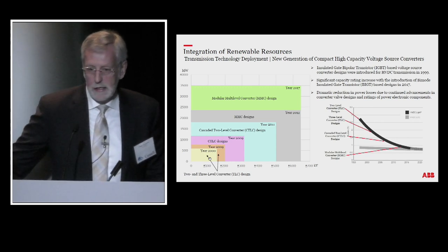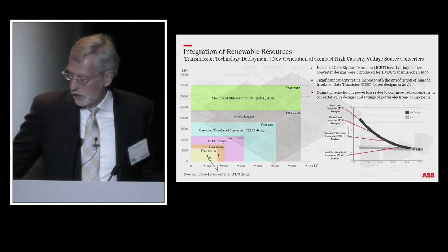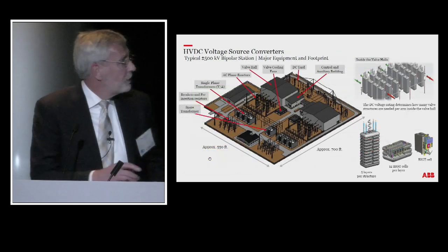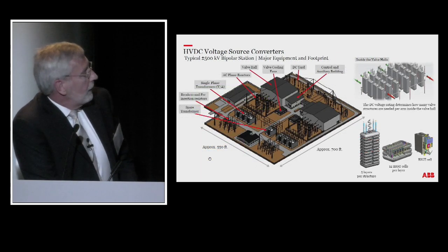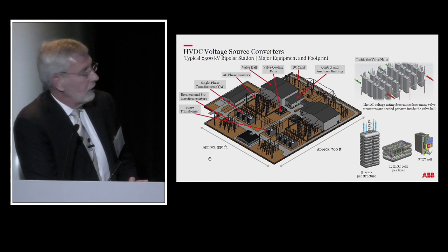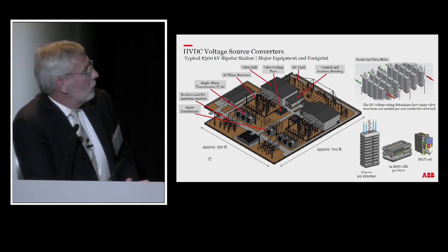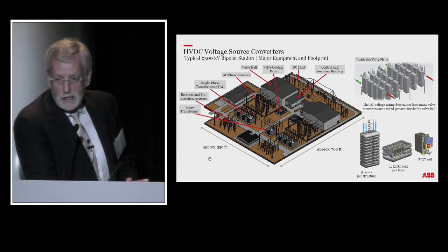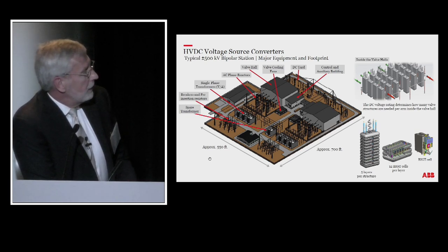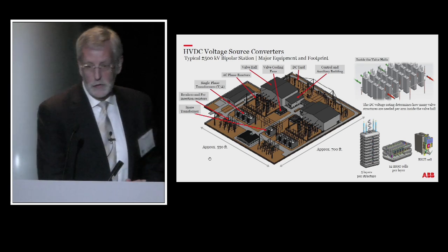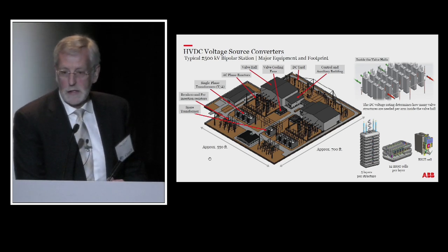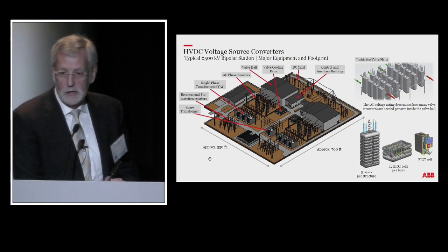So definitely suitable for large scale transmission. I already mentioned footprint—this is an example of a plus-minus 500 kV bipolar station, with a capacity rating of around 3,000 megawatts, that can fit within a footprint of 700 by 550 feet.